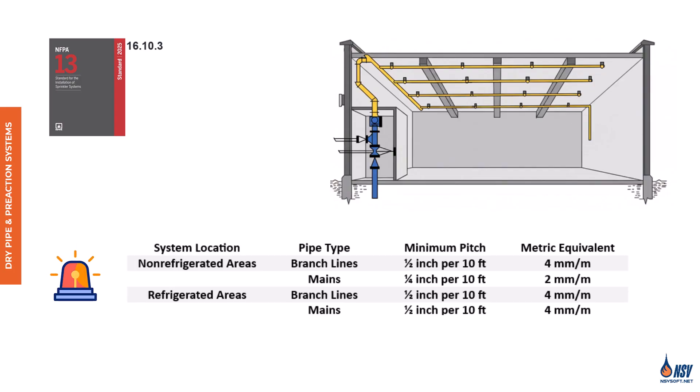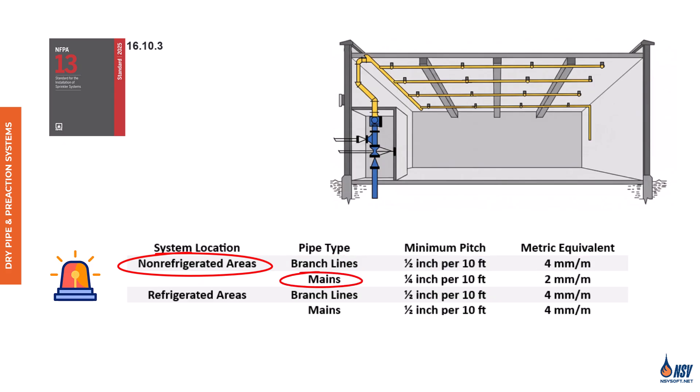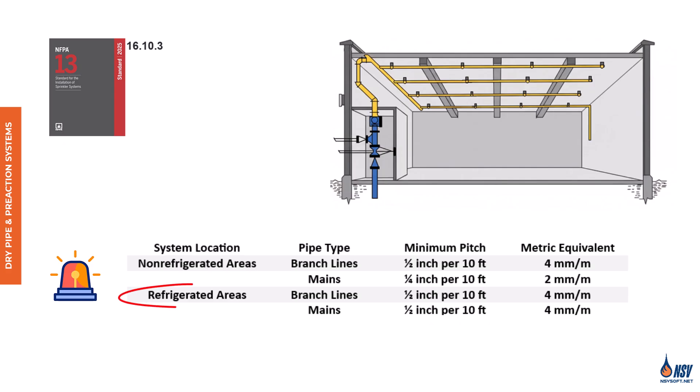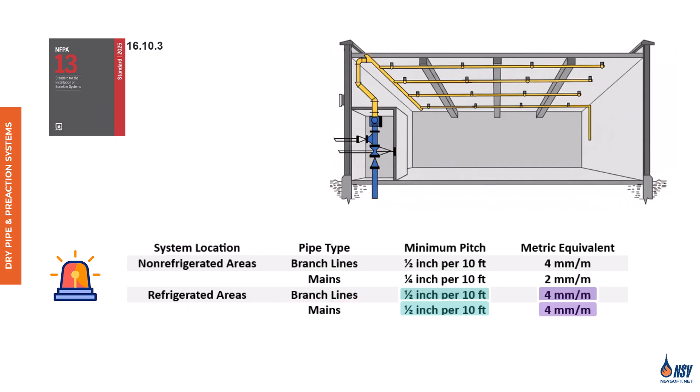According to the table, in non-refrigerated areas for both dry pipe and pre-action systems, branch lines must be pitched at a minimum of one-half inch per 10 feet, equivalent to four millimeters per meter. Main lines require a minimum pitch of one-quarter inch per 10 feet, or two millimeters per meter. For dry pipe and pre-action systems in refrigerated areas, the pitch requirements are more stringent. Both branch lines and main lines must be pitched at one-half inch per 10 feet, four millimeters per meter. This steeper pitch helps ensure complete drainage, minimizing the risk of ice formation and system failure.